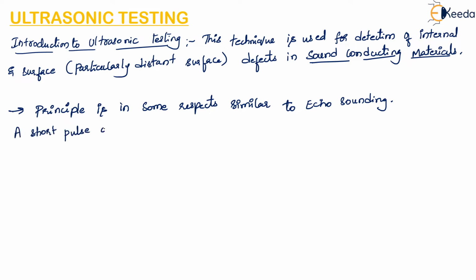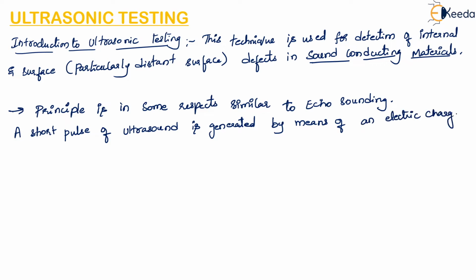So here a short pulse of ultrasound is generated by means of an electric charge applied to a piezoelectric crystal.